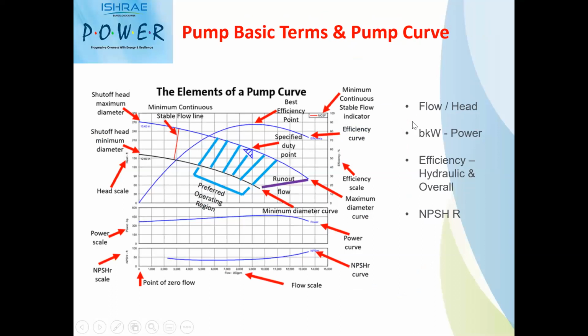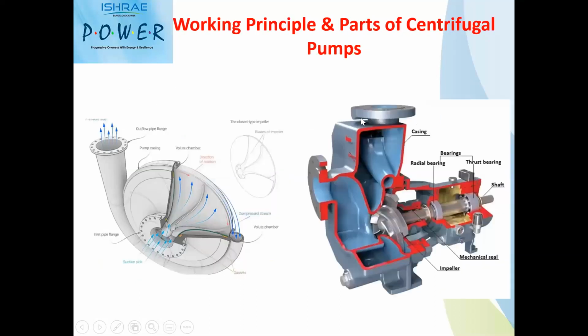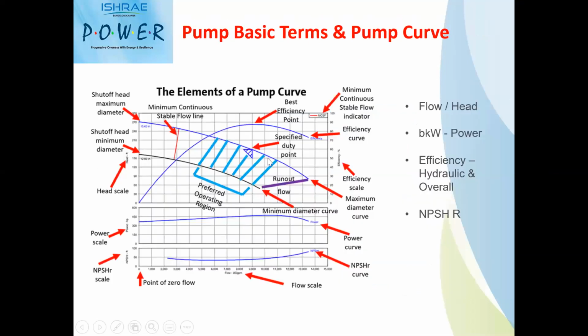The head value is decided based on the impeller size. The bigger the impeller, you will have more head. That relation is arrived by the affinity law. So when a typical pump requirement comes, it will require minimum parameters like flow and head out of the pump, based on which I will be selecting a pump typically for this duty parameter.